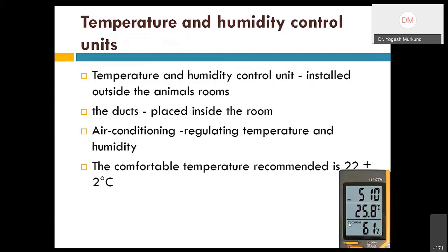Temperature, we know that it is very important. We discussed that the control units for temperature and humidity should be kept outside the room. Display can be inside, so they can take the readings, but the units should be outside so that there is no dust formation on them.